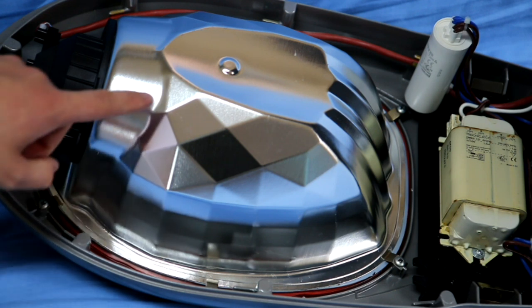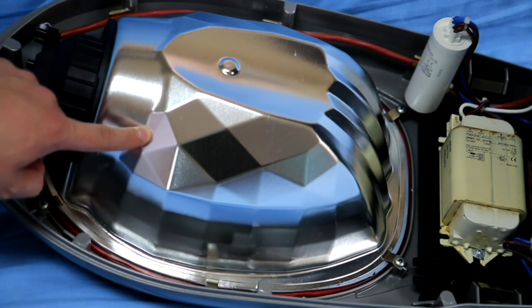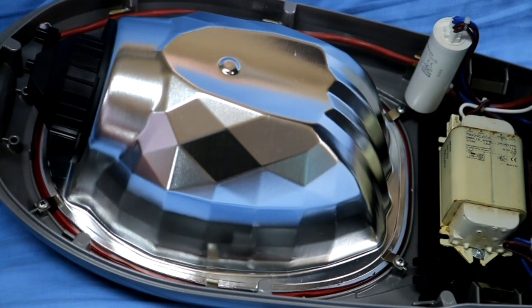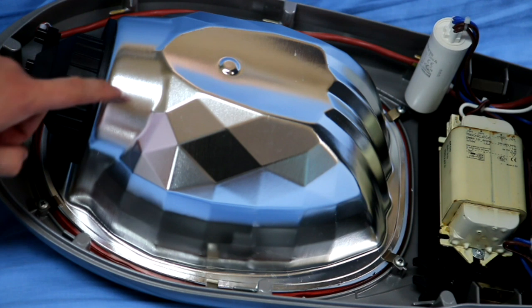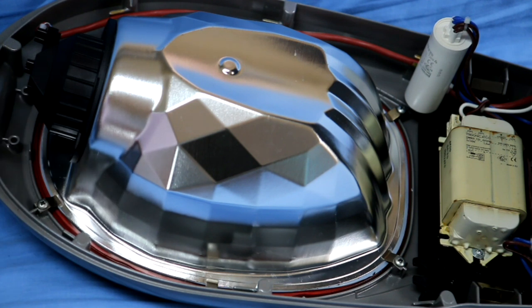Double ingress protection. You can get this with just the reflector which bolts onto the canopy like the old Philips, but I think most people choose this for the improved lumen maintenance and you don't have to clean it every time you relamp it, it's just job done.